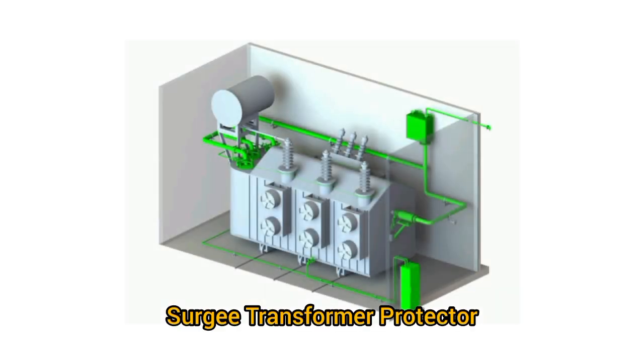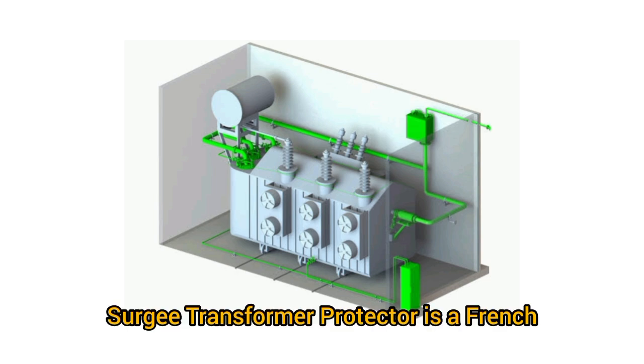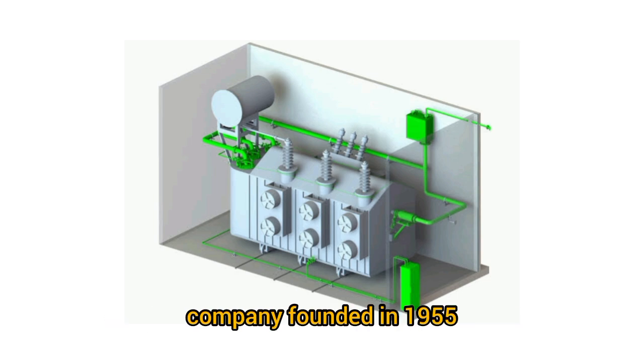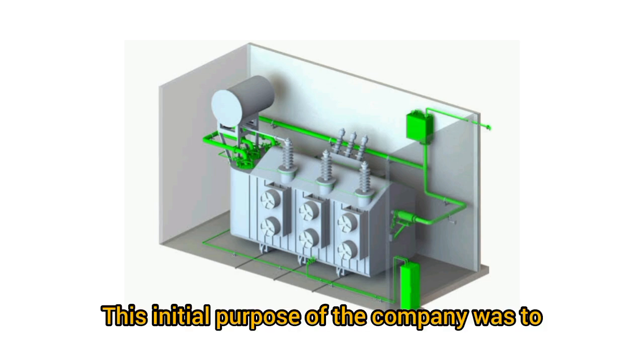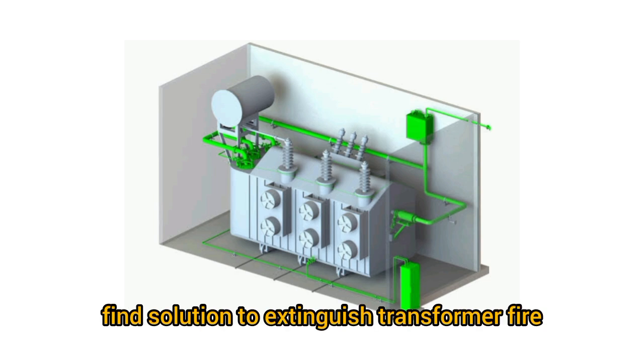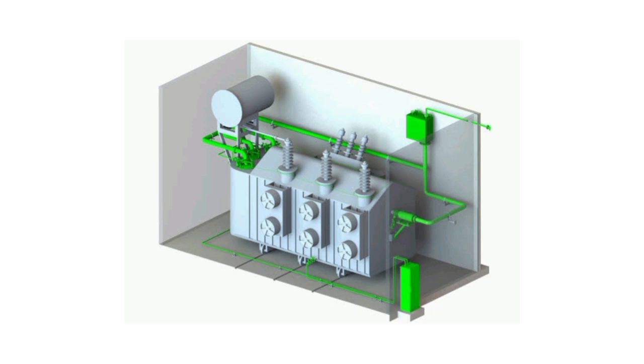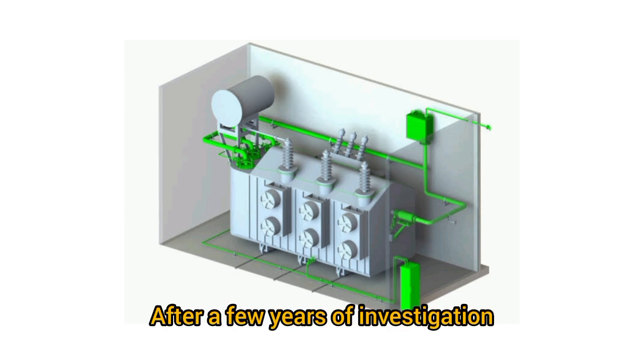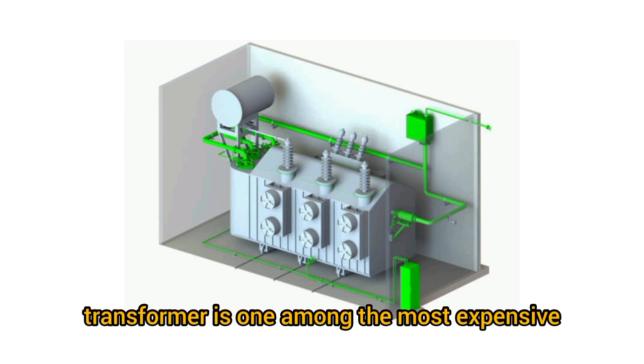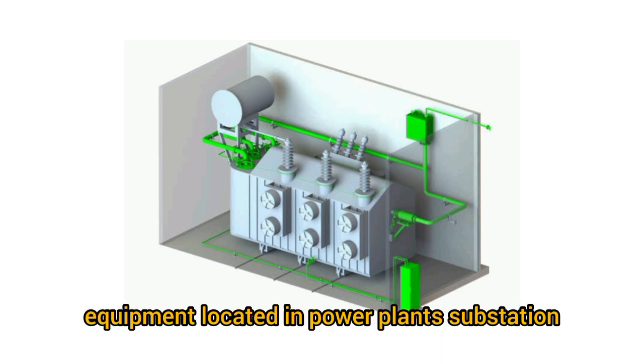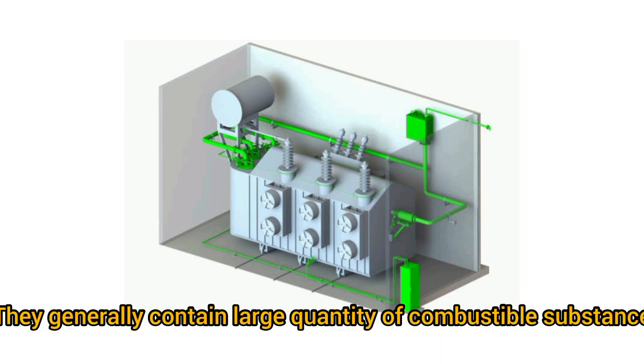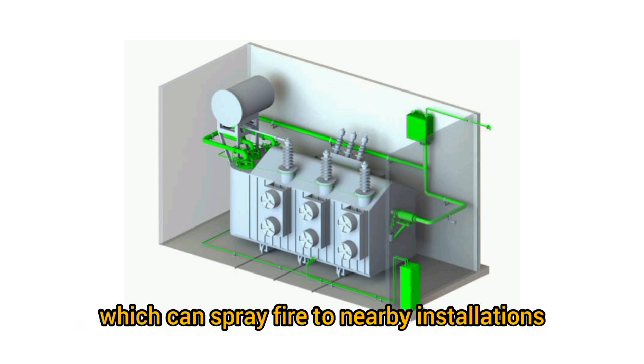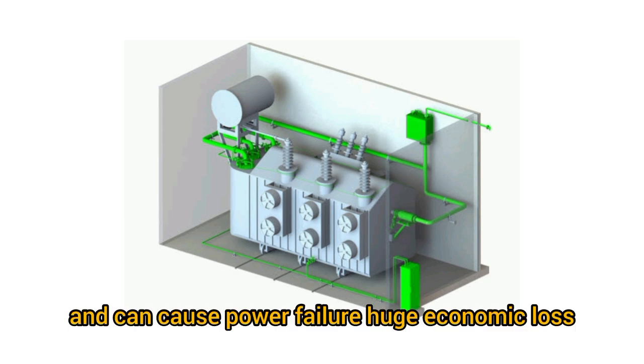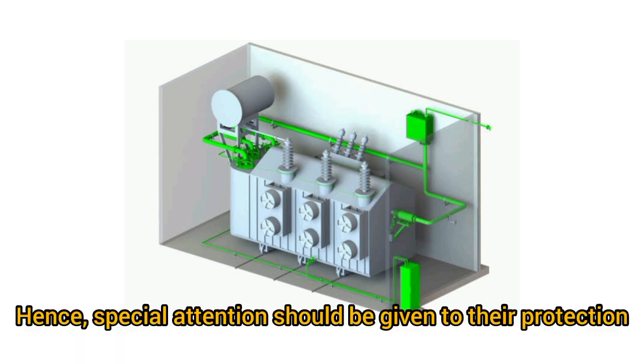Sergi Transformer Protector is a French company founded in 1955. The initial purpose of the company was to find a solution to extinguish transformer fires. After a few years of investigation: the transformer is one of the most expensive pieces of equipment located in a power plant's substation. Transformers generally contain large quantities of combustible substances which can spray fire to nearby installations and can cause power failure and huge economic loss. Hence, special attention should be given to their protection.